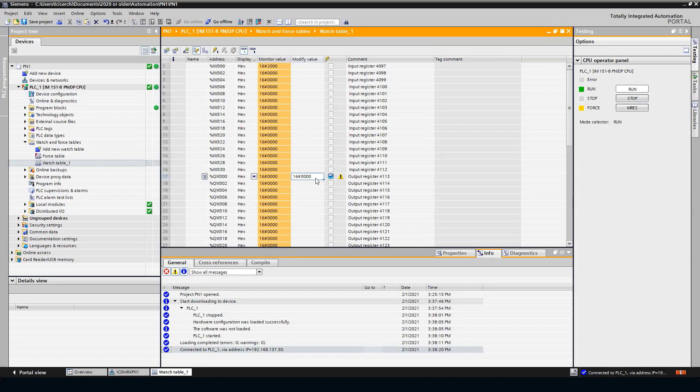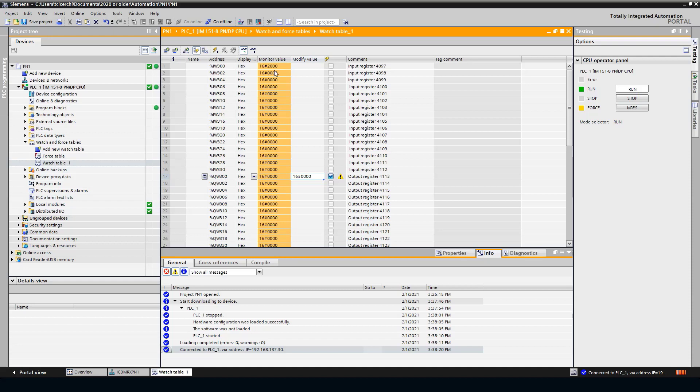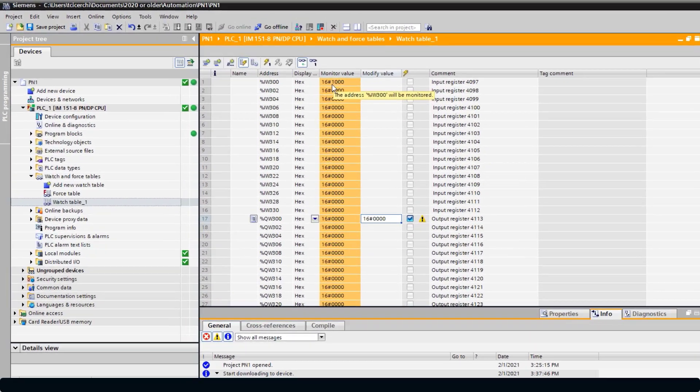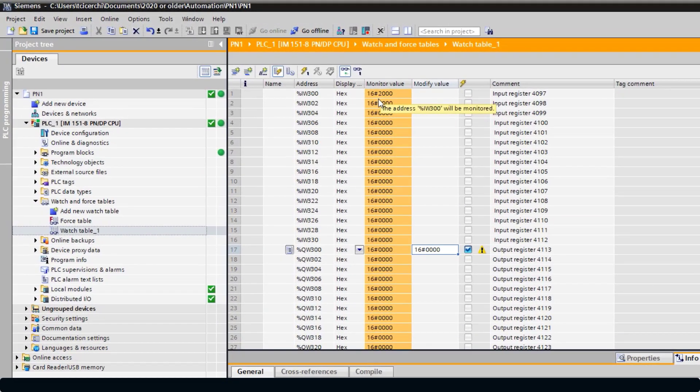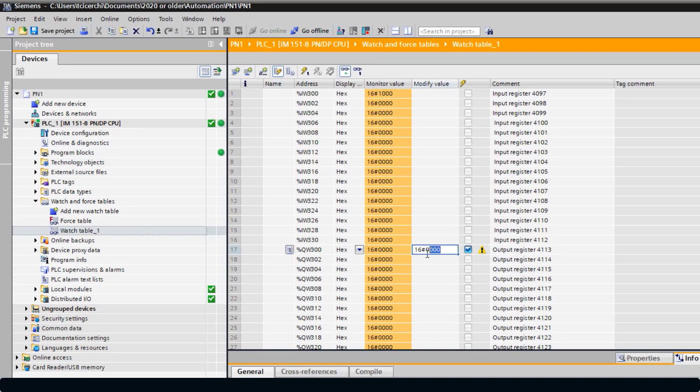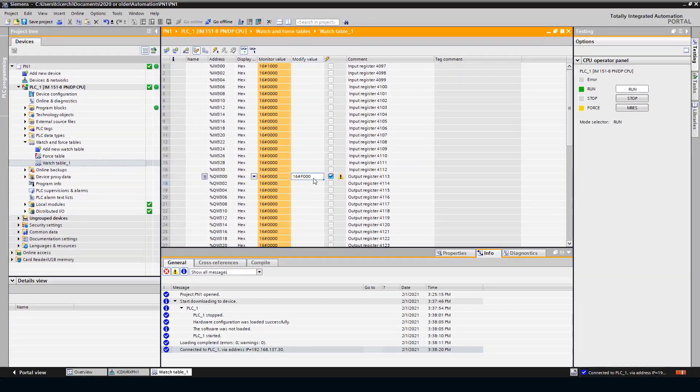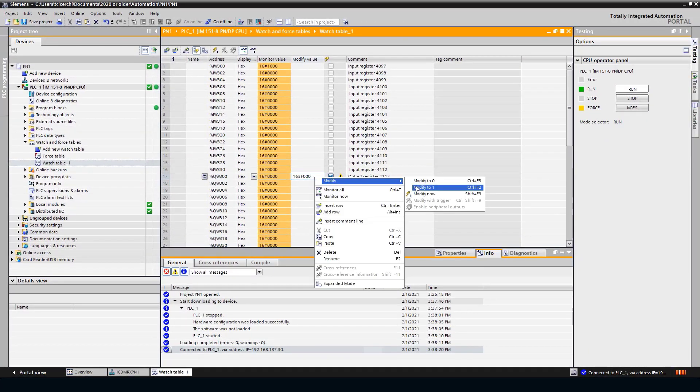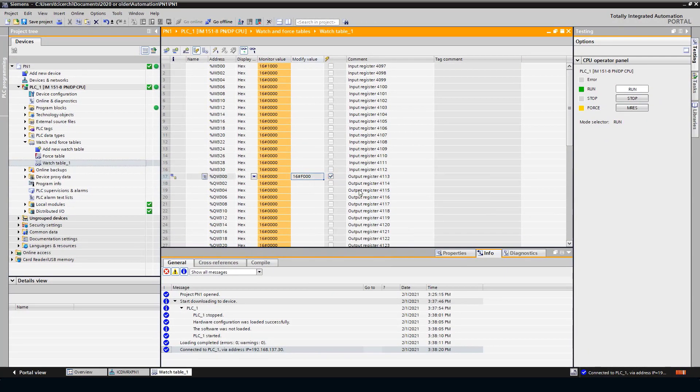All right. I downloaded my project. Everything looks great. I went and set up a watch table. So, IW300, so IW330 for my inputs, QW300 for the outputs. And I got my PhotoEye on my ASI module one. You can see it right here. I'm moving it back and forth. You can see it switch. Also, if I want to force the outputs on, I want to turn all the outputs on for that module. And I'll just right click and force. And that's it. Pretty simple.